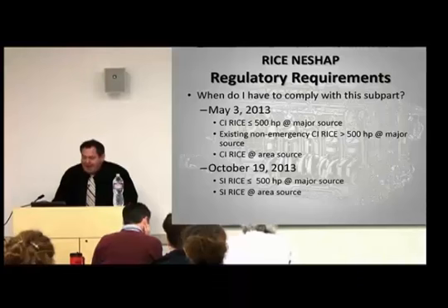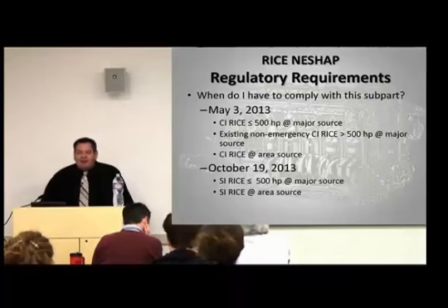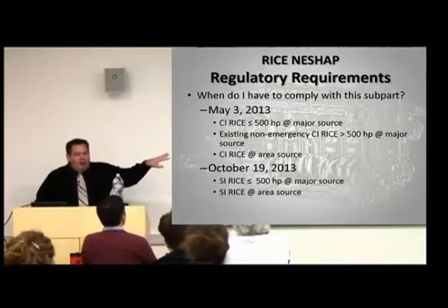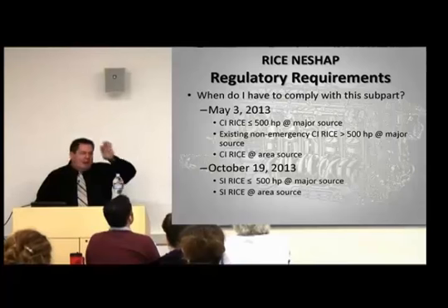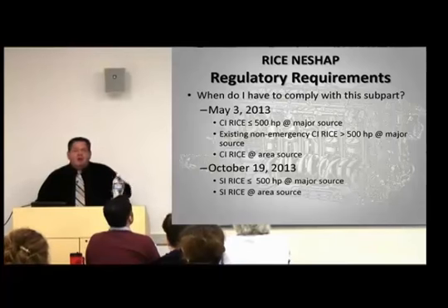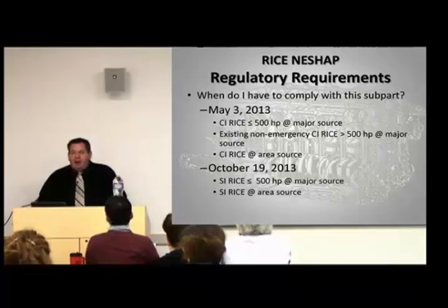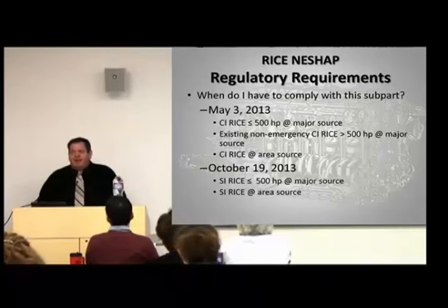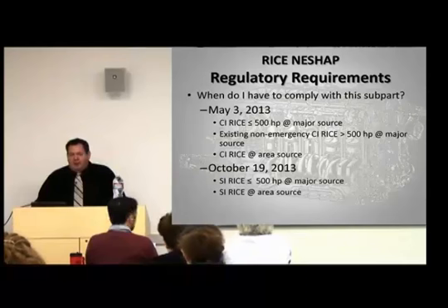Questions? Hearing none. Let's talk about compliance dates. There's probably 6 or 7 compliance dates that have passed. The 2 compliance dates that are looming on the horizon are May 3rd of this year for compression-ignited engines, October 19th of this year for spark-ignited engines.